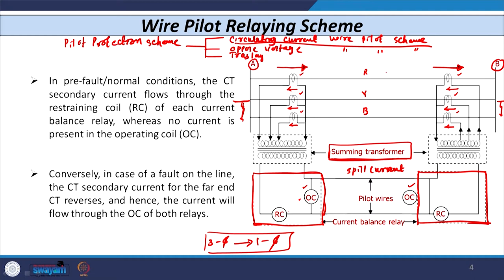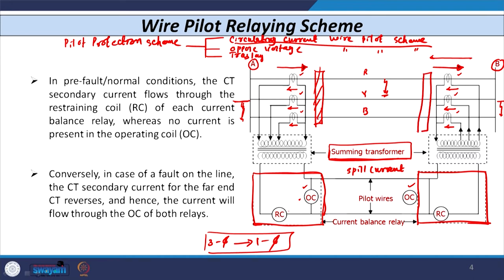In case of an internal fault, the direction of the CT current changes because it now feeds the fault. This causes the current to flow through the operating coil of the relay, which operates and gives a signal to the respective breaker. Both the breaker at substation A and the breaker at substation B open simultaneously, and the fault is detected.